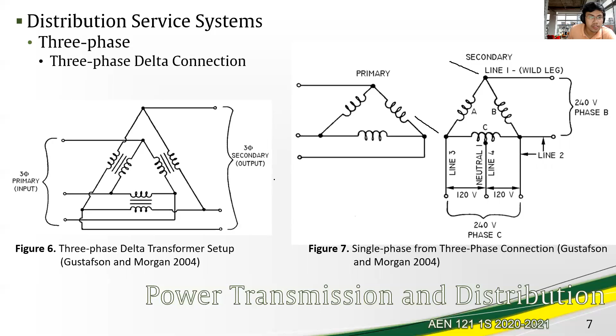Now the problem with this situation is you have to balance the use of all the phases: phase A, phase B, and phase C. You have to balance the load among these phases if you're going to make use of a single phase from a three-phase connection. It would be much better, if you're going to use a single phase, to connect separately to the main line or to the service entrance.